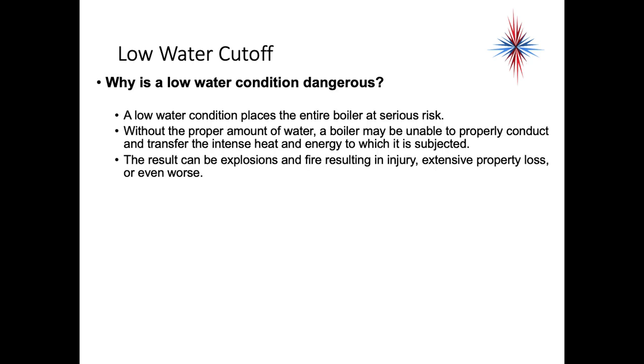A low water condition places the entire boiler at serious risk. Without the proper amount of water in a boiler, it could be unable to properly conduct and transfer the intense heat and energy to which it is subjected. The result can be explosions and fire resulting in injuries and extensive property loss — if a boiler actually boils water where it's not designed to, the water flashes to steam and can actually explode the boiler vessel. This happened much more frequently in commercial and apartment buildings, particularly in New York City in the late 1950s and early 1960s, before they started putting in low water cutoffs.